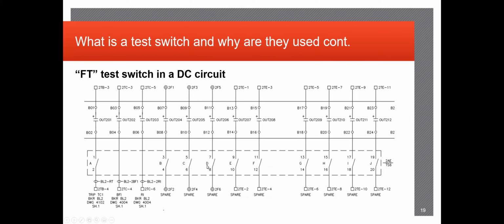If you're looking at the prints, you can identify the test switches usually associated with the DC schematics. Again, their primary purpose is to break the circuit in and out of the relays. So for instance, here this is the relay itself identified right here with its output contacts. You have terminal blocks associated up here, and then you have your test switches to either make or break the circuit. So in this instance, test switch A, which is associated with the out 201 contact in this relay, is actually a trip coil contact going up to the breaker.